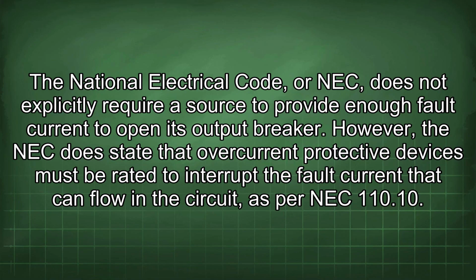National Electrical Code, or NEC, does not explicitly require a source to provide enough fault current to open its output breaker. However, the NEC does state that overcurrent protective devices must be rated to interrupt the fault current that can flow in the circuit, as per NEC 110.10.